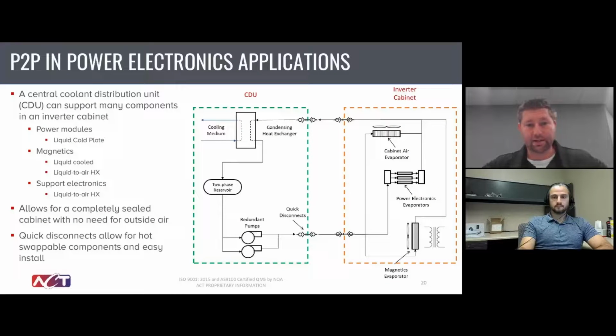This slide gives a view of the circuitry that goes on in one of these systems. In many cases, you have a coolant distribution unit, which houses your balance of plant or the componentry that drives the pump two-phase system. Then you have your evaporators within, in this case, an inverter cabinet or electronics cabinet, which are coupled directly to your power sources.